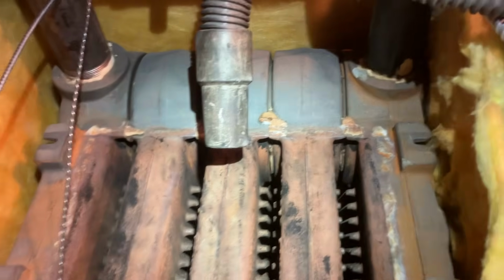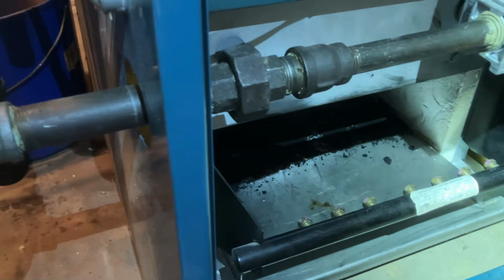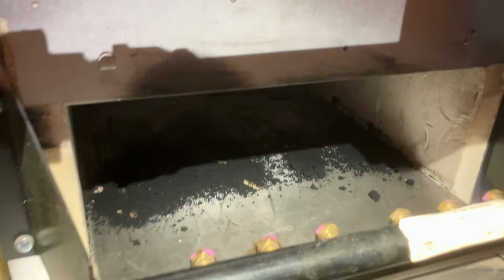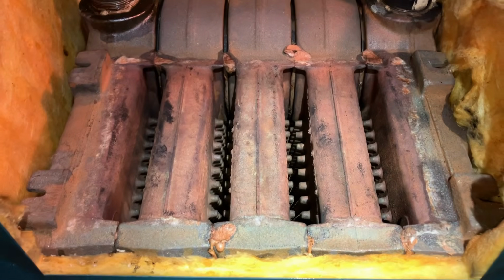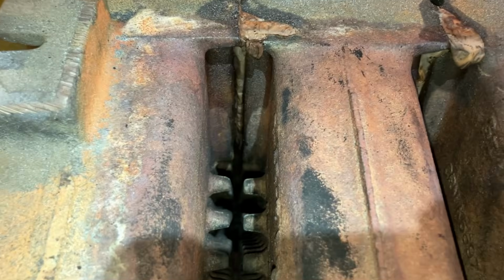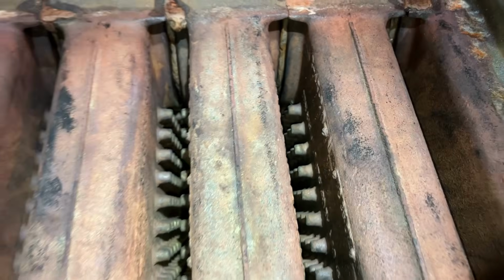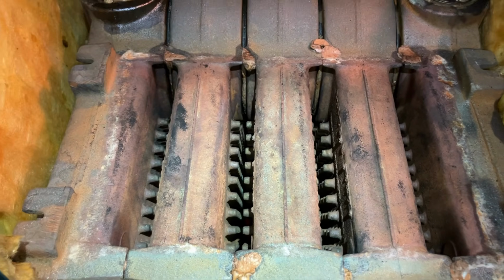All right, I just finished up pass number 4. All right, much better. Let's vacuum this out. And then do number 5. All right, pass number 5. Just a little bit in that corner there. Excellent. All right, now that my heat exchanger is clean, it's time to reassemble the boiler.